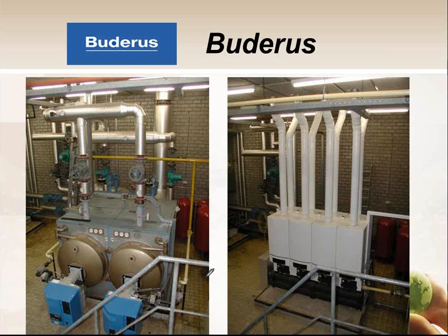Dan's clarifying his question, saying he means just the boiler, and the answer to that is no also. So these are low-mass boilers, so they just have a coiled-up heat exchanger in them. Like a 200,000 BTU boiler may only have 2 gallons of water in it, and it's moving through there at a fairly high velocity, so that water's not sitting in there. Now, we do have to do some stuff to clean the boiler, but most of what we do is going to be on the air side, the combustion side. We will have to open up that burner, take it out.